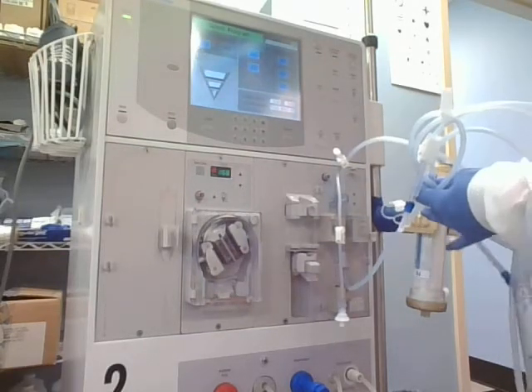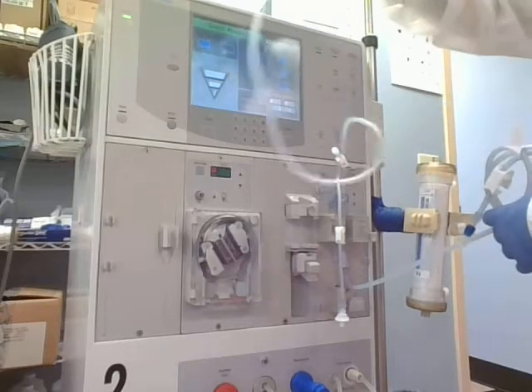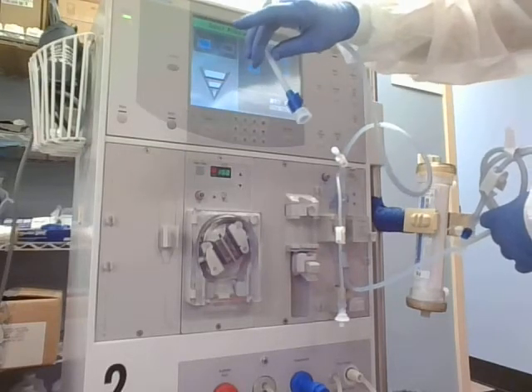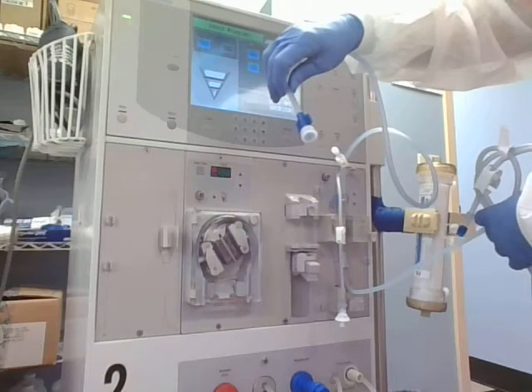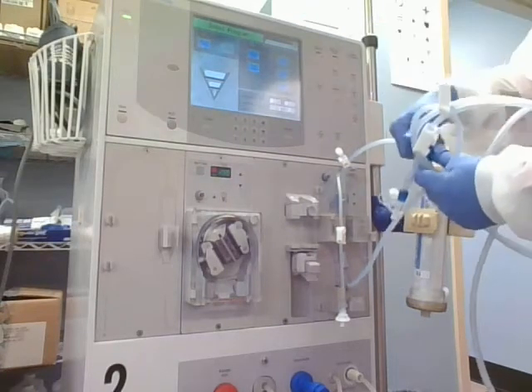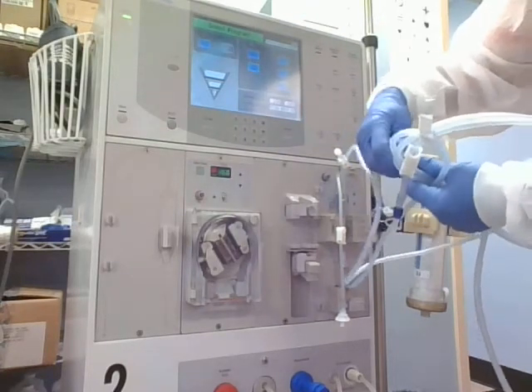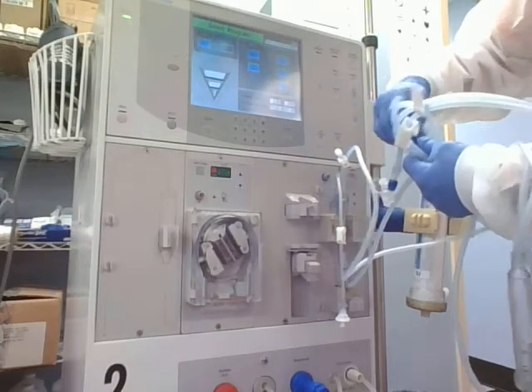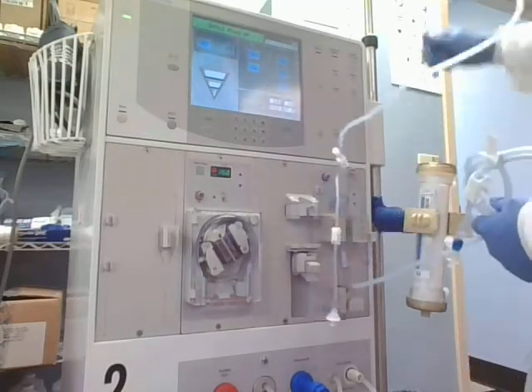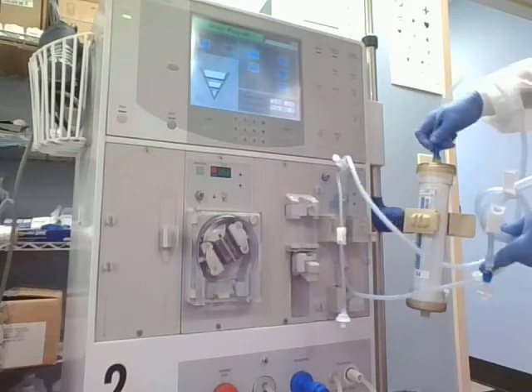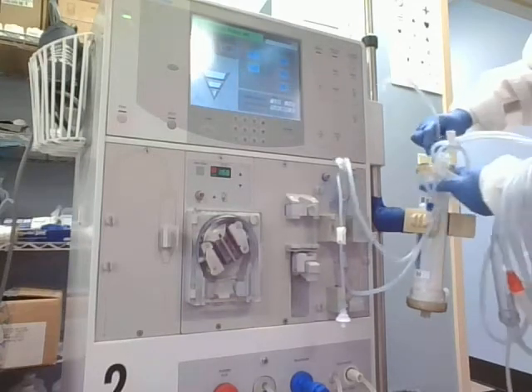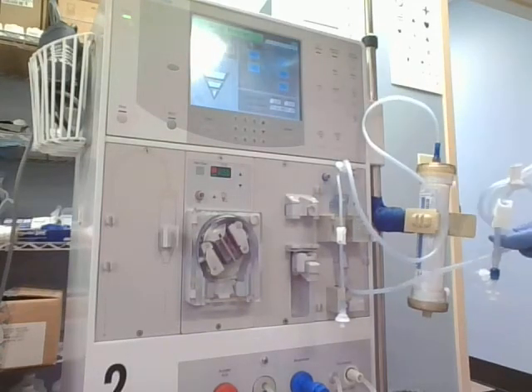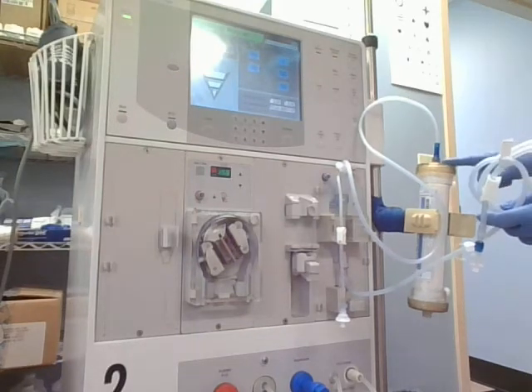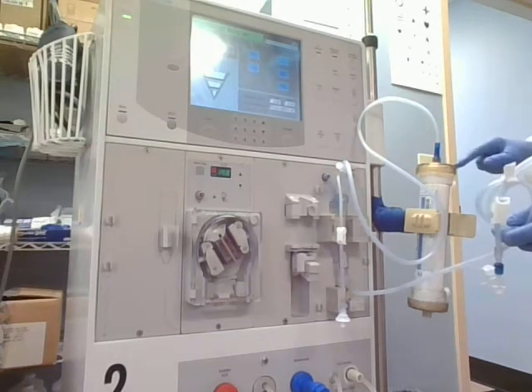The next step that we're going to do is, since I took my tab off of this line, my dialyzer connector is next in line. So I'm going to take the cap off of my dialyzer connector, and that should just pop right off. And I'm going to connect my dialyzer connector to the venous port on the bottom. This is actually the bottom. Remember, we have it inverted for priming.